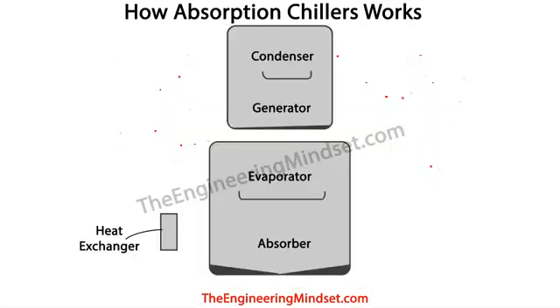Okay, so now that we know the very basics of what's happening inside, let's look at the main components of there. So in the top chamber, we'll always have the condenser and the generator. In the lower half of the chiller, we'll always have the evaporator and the absorber. And then on the side, down below, near the bottom, we'll also have a heat exchanger. The heat exchanger is just there to improve the efficiency of the system. So it will transfer heat that's coming from the generator into the liquid which is coming from the absorber. And we'll see that in just a moment.